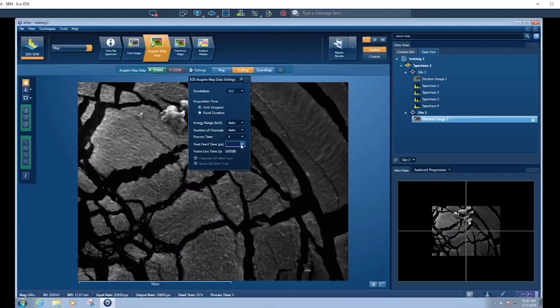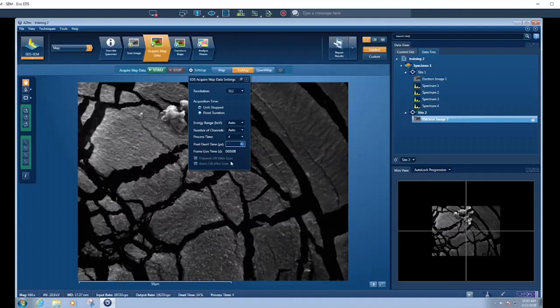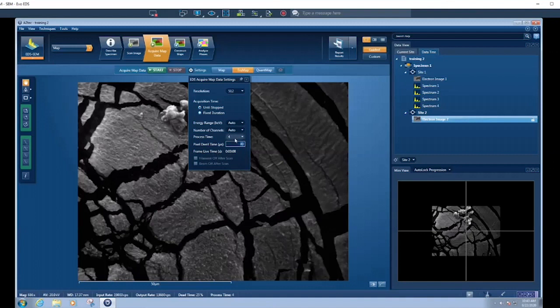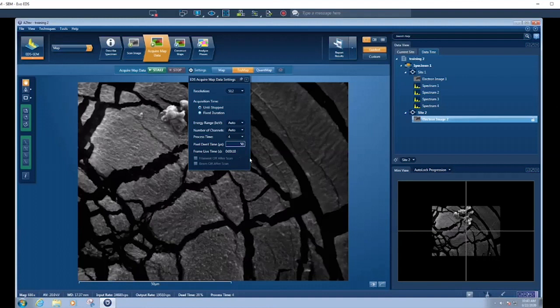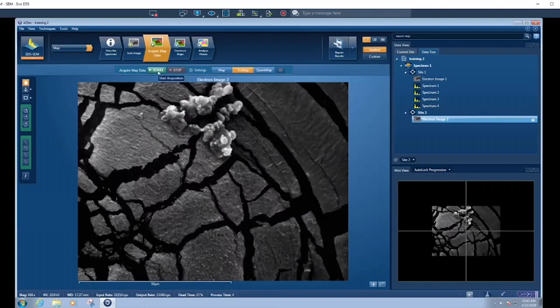If we choose to quantify large areas, we can do that using this though. If we were to be looking at an area that we're not so worried about what the individual compositions are, but more the overall composition and just be sure that it's homogeneous, then we can just count for the same amount of total time. But the take home message here is choose a pixel dwell time that creates a frame live time that is not too large. In this case, we want to be aiming for less than one minute. We want to keep the frame live time less than a minute so that we can make sure that we're not drifting too much in between each scan.